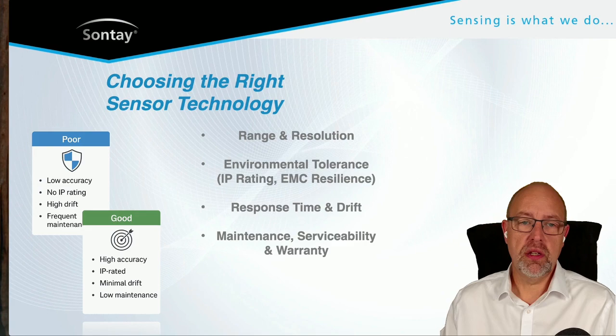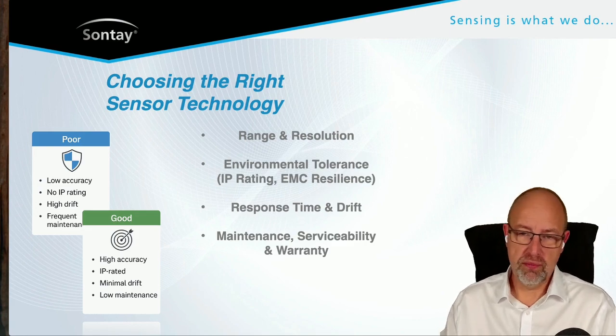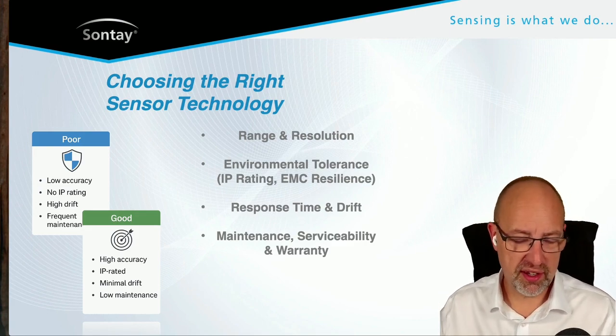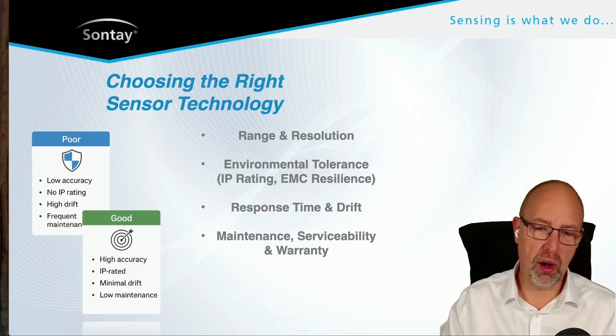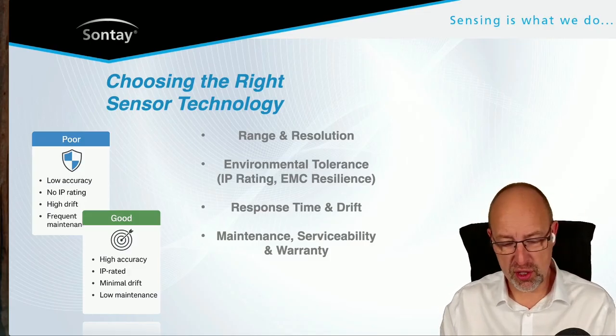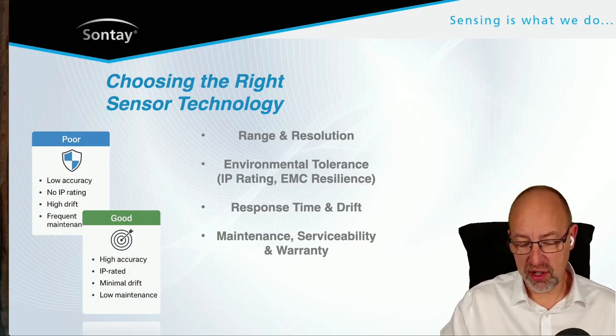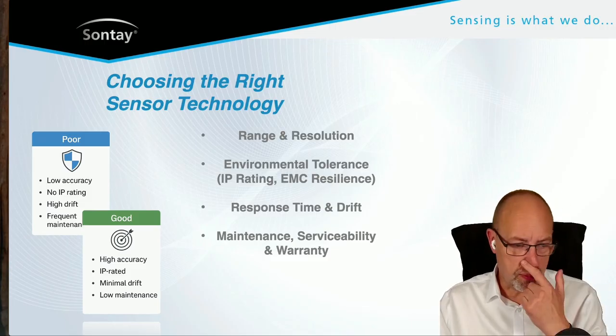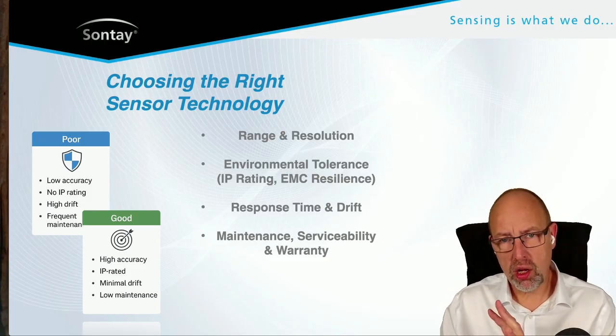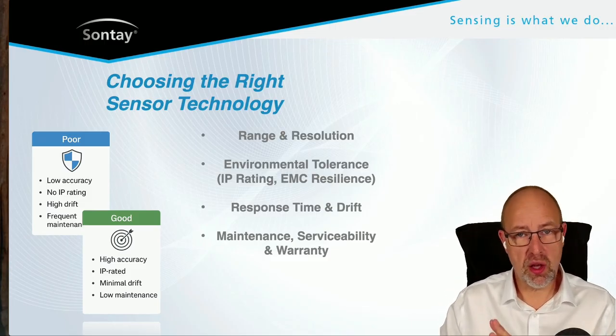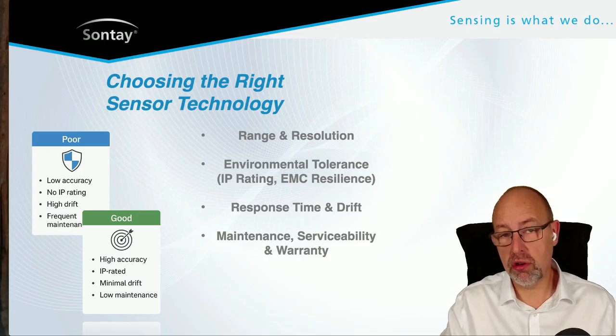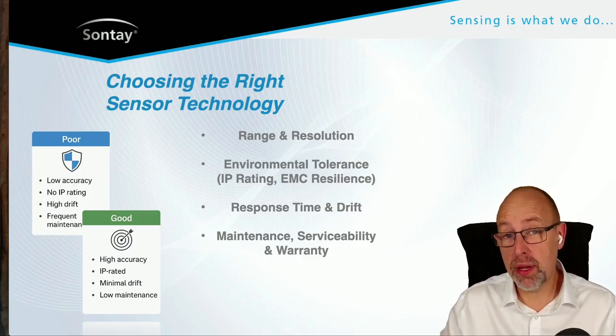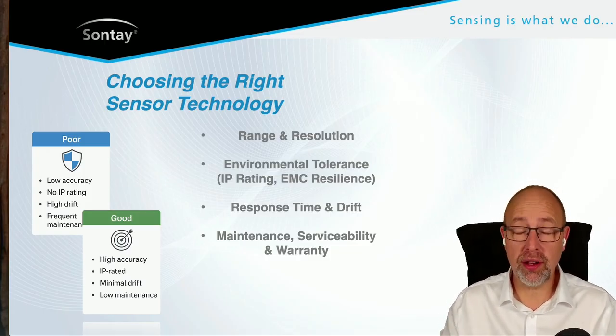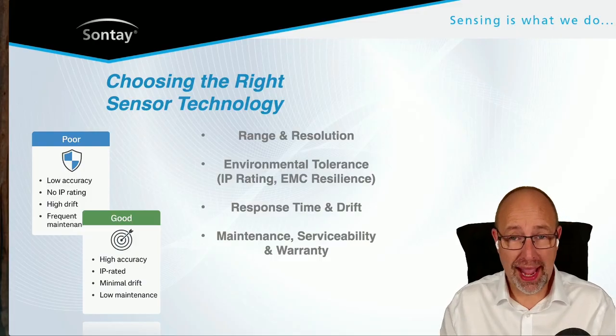Choosing the right sensor technology, well, just choose a Sontay one, obviously. But beyond that, why? What particularly do you want to choose from the Sontay range? Range and resolution are really important. If you are choosing a sensor which has got an active output, a 0 to 10 volt output, it needs to be within the right range so that you get good resolution, accurate data.